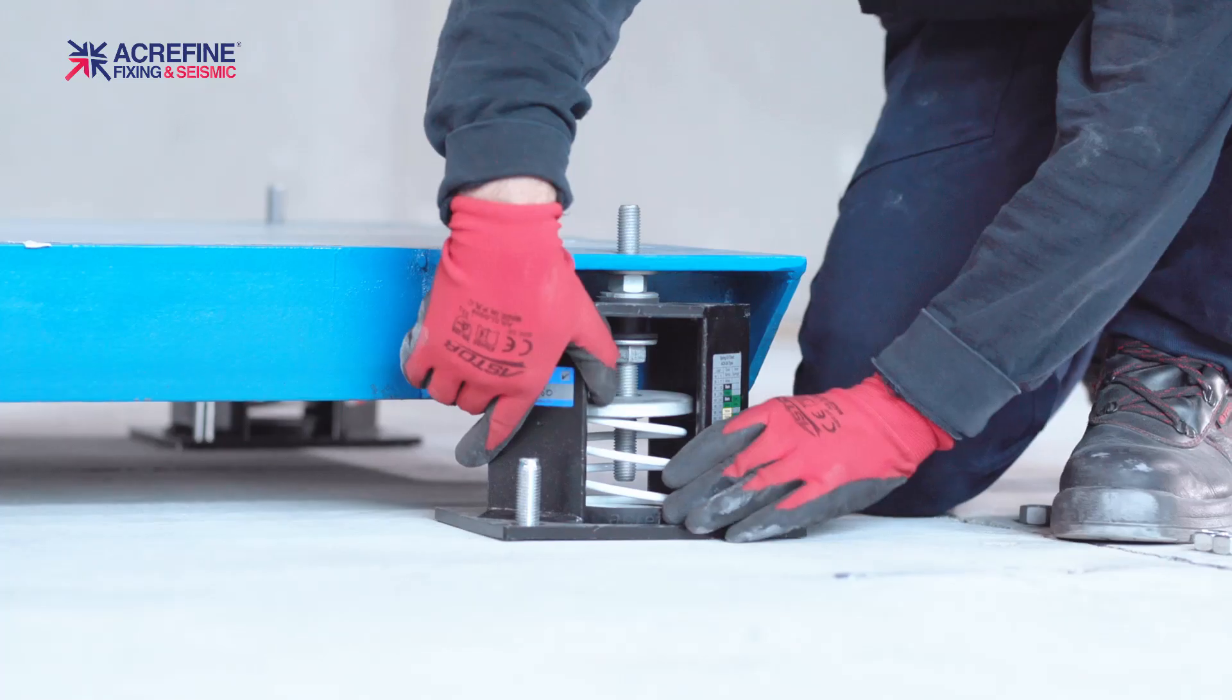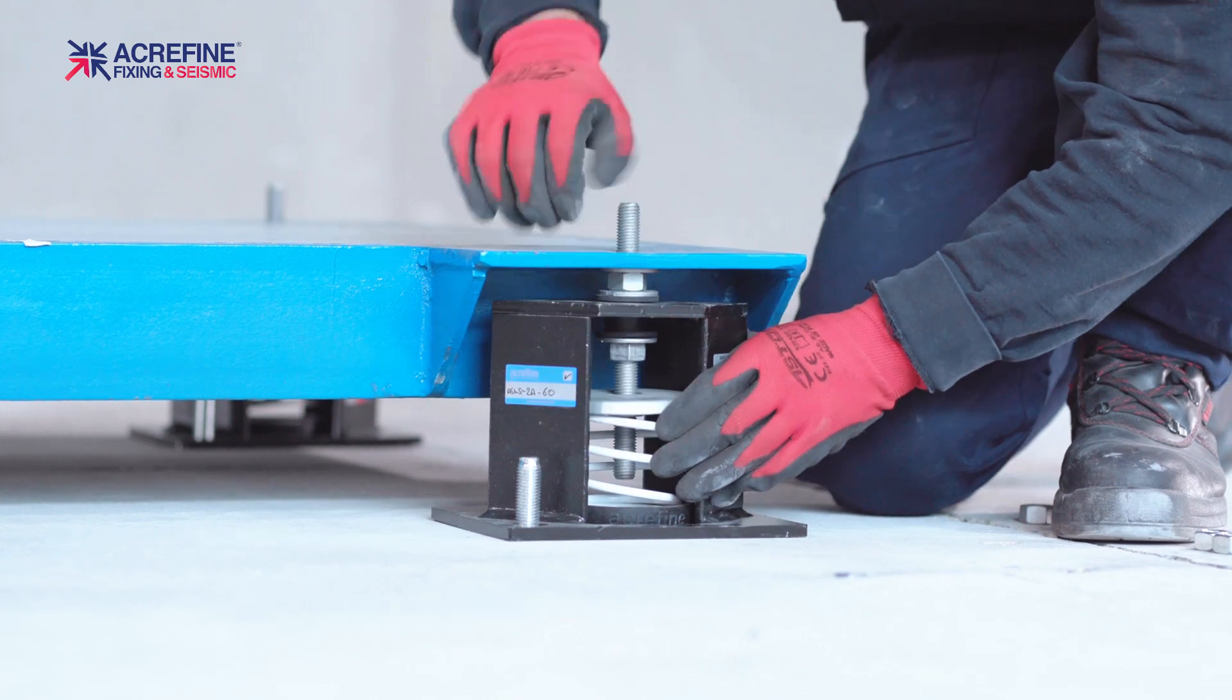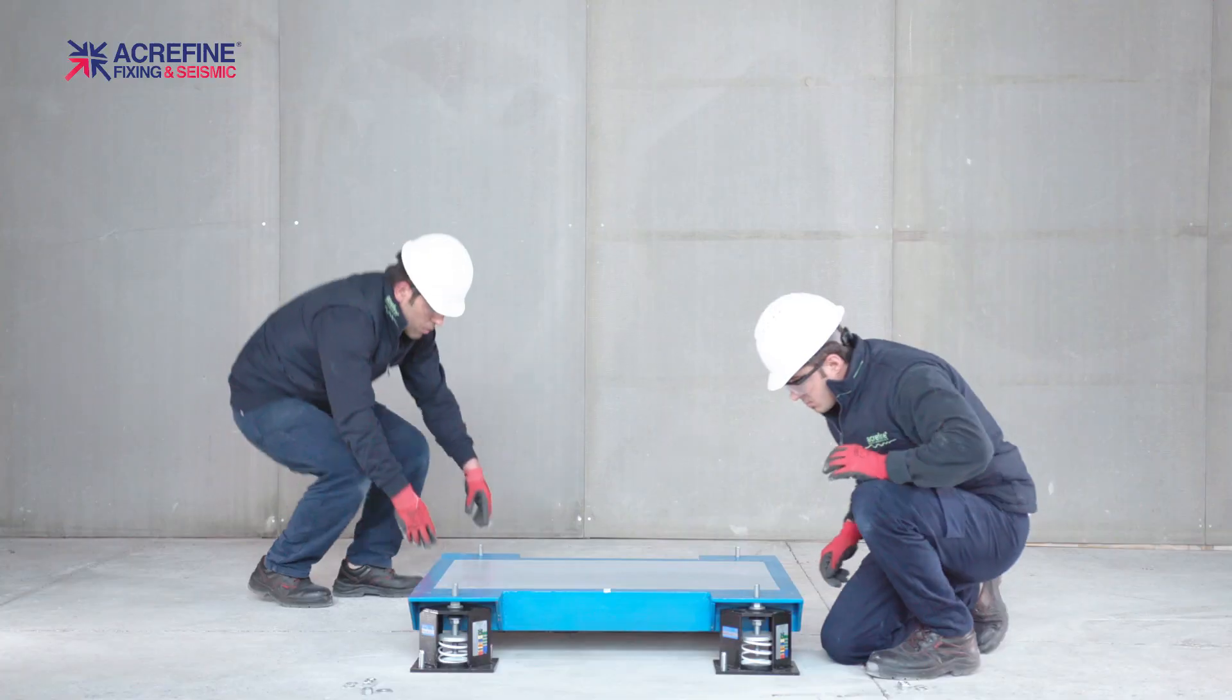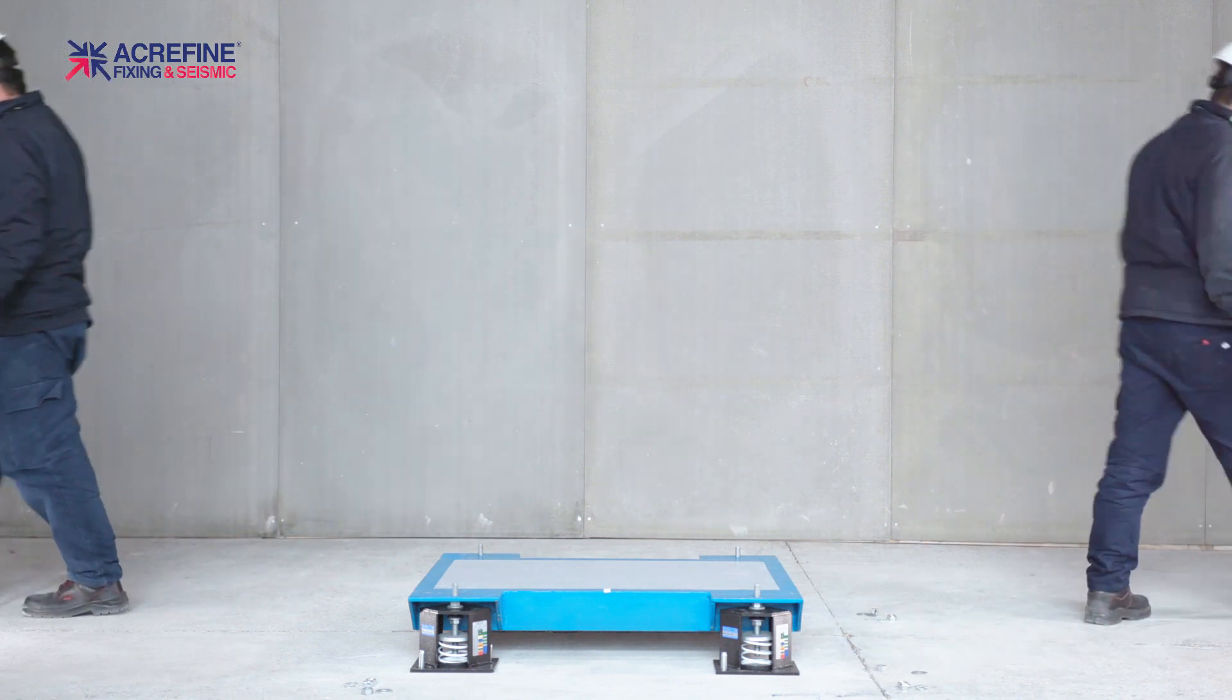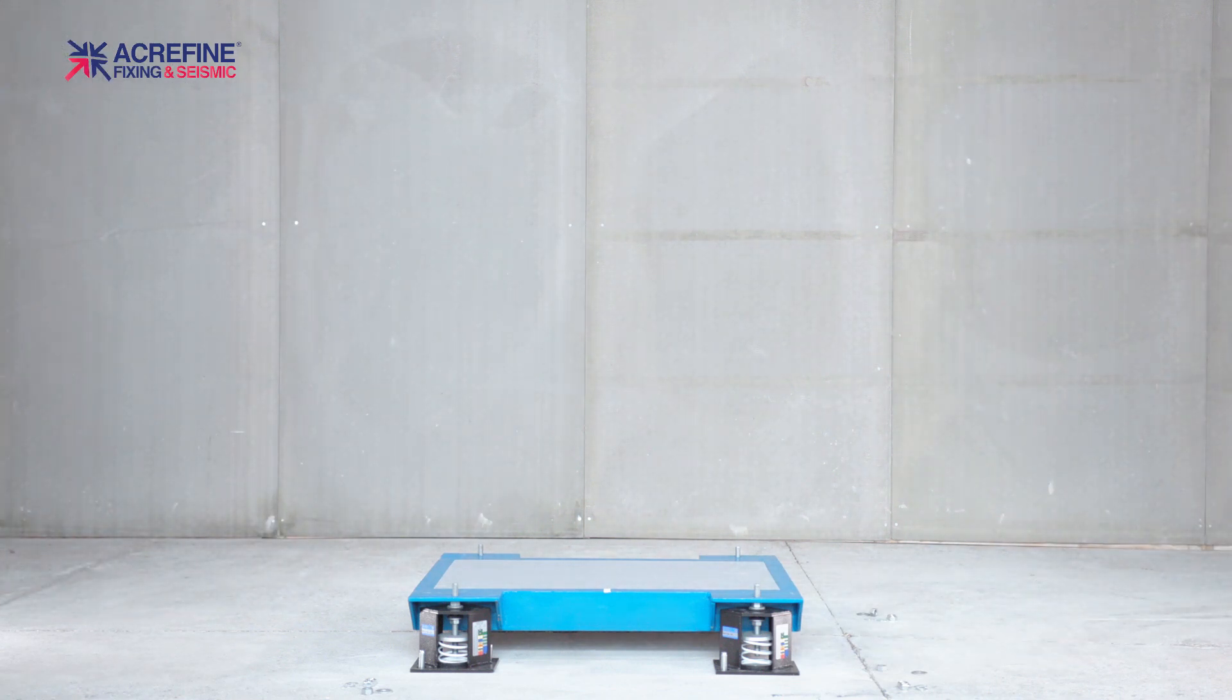To make sure the base is properly placed, check the springs. They should be perpendicular to the ground. If necessary, you can slightly move the isolators as much as the anchor bolts allow for.